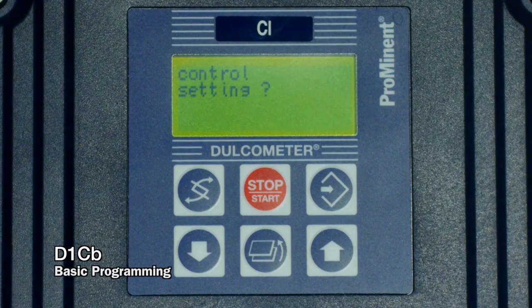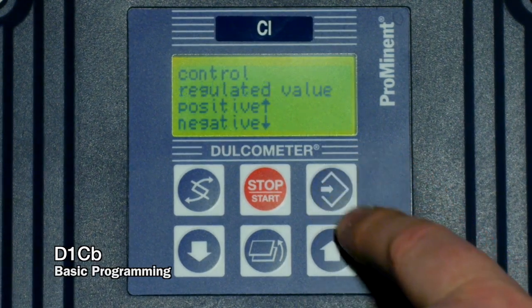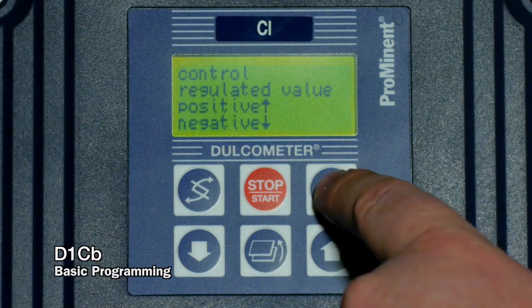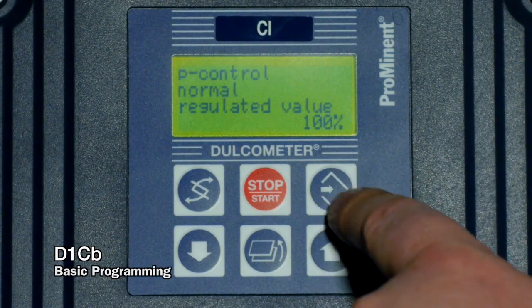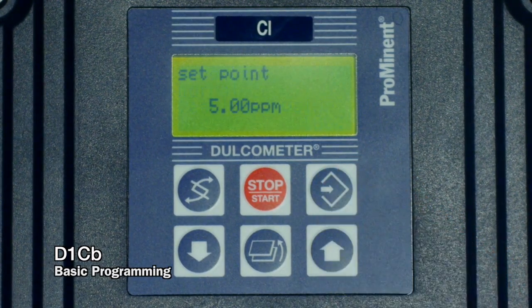control settings. We enter that with the enter button, the top right-hand button. Continue to hit the enter until you get to set point is flashing. You'll see that here the set point is at 5 ppm. The set point goes to half the measuring range. Keep that in mind if you change that measuring range and change it back. Several things go to their default setting, including this set point.